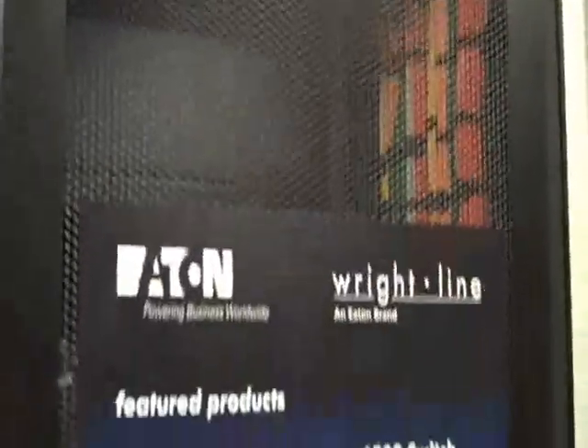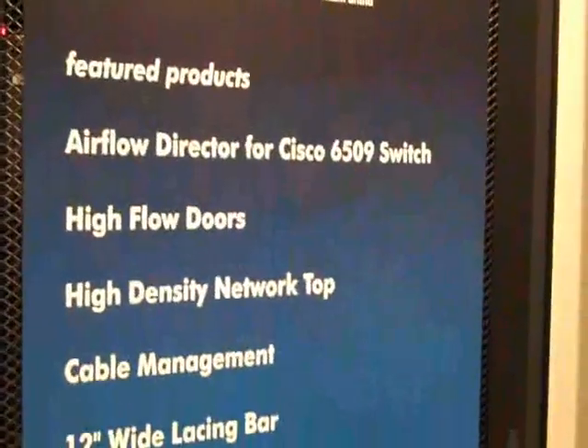Sure. This containment system happens to be a freestanding, independent containment system. We have vertical blanking panels on this wall. These entire vertical blanking panels can be removed, and a rack could be rolled up to these vertical blanking panels. And on the opposite side, we show some racks already configured into this aisle that has spaces above and below. As you see, this aisle is configured of different sizes and shapes of racks. Containment, particularly independent containment, allows a total containment. It doesn't matter what type of rack, and you're able to maintain the containment integrity all around the rack and seal the aisle, gaining the user the most possible efficiency by managing their airstreams in this type of system.